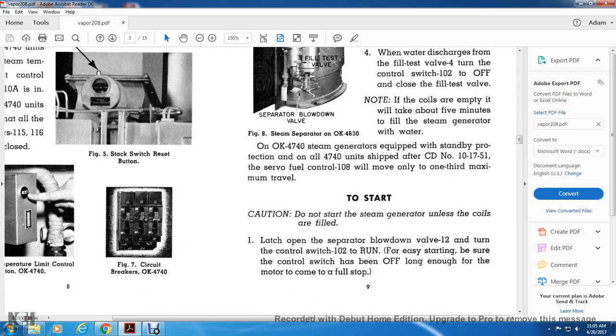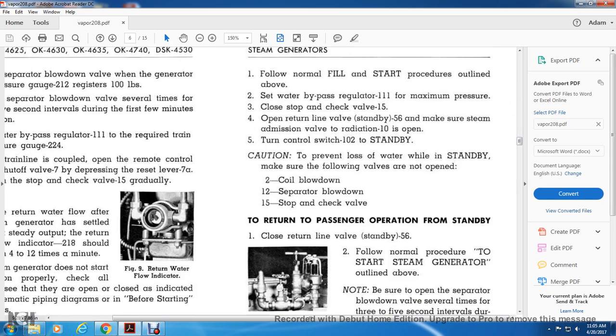Alright, to start, do not start the steam generator unless the coils are filled. Latch open the separator blowdown valve 12 and turn the control switch 102 to run. For easy starting, be sure the control switch has been off long enough for the motor to come to a full stop.